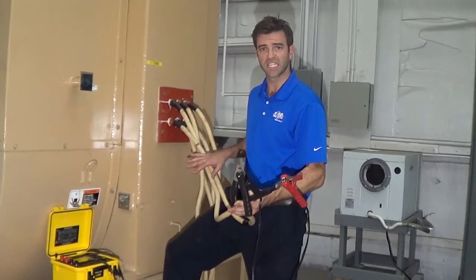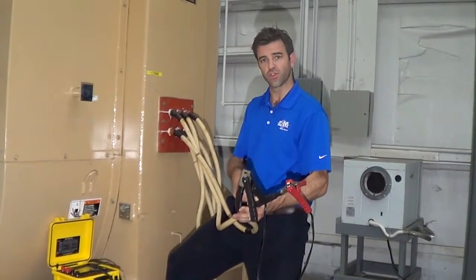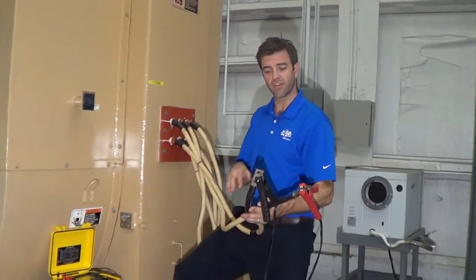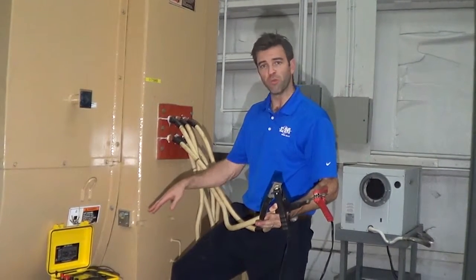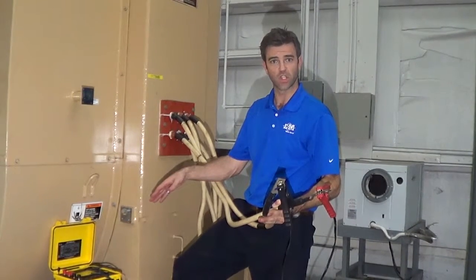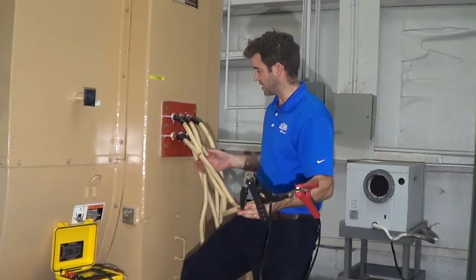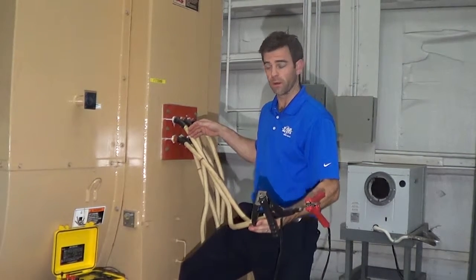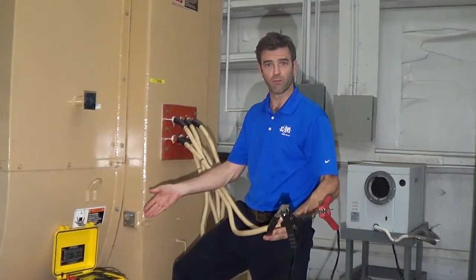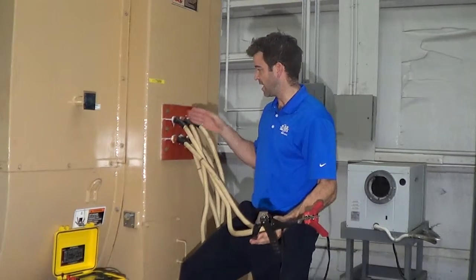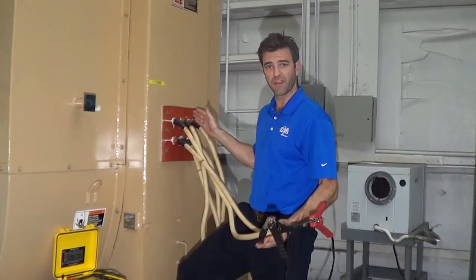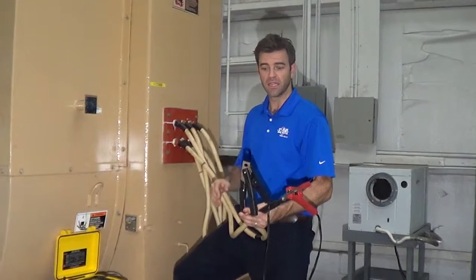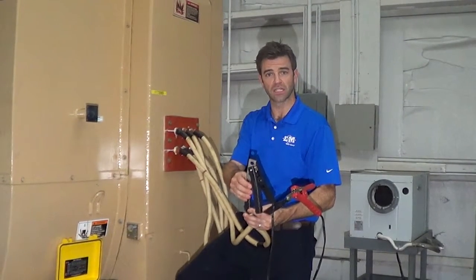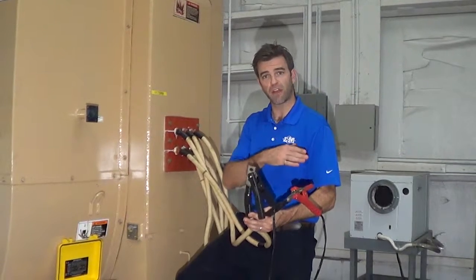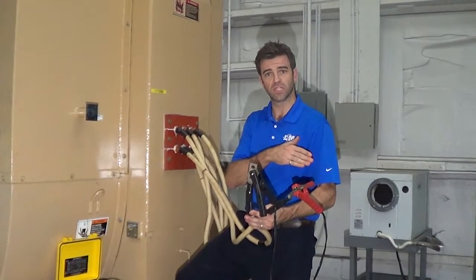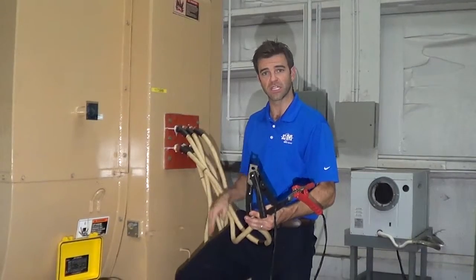Now that we've completed the insulation resistance testing, we want to measure the resistance of each phase. You can see here I have the 2 leads of a milliohm meter, sometimes called a digital low resistance ohm meter or DLRO device, connected to phase A, or leads 1 and 4. Many automatic testers will perform the same test, but the result is a resistive imbalance of each of the 3 phases. High resistive imbalance is typically a result of poor lugs. You may also check the resistance back from the switchgear room, and that will tell you the resistance of the complete cable set, including the stator leads.